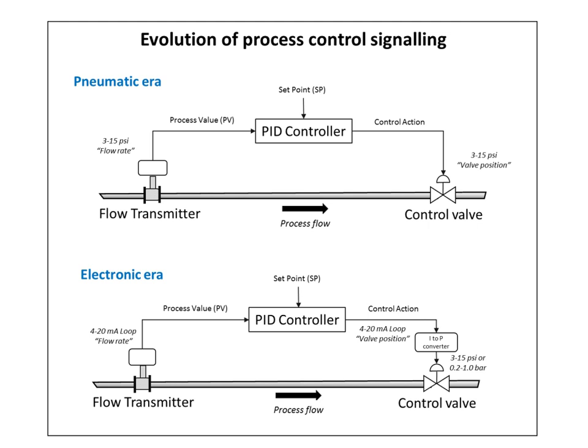Transistor electronics enabled wiring to replace pipes, initially with a range of 20 to 100 mA at up to 90 V for loop-powered devices, reducing to 4 to 20 mA at 12 to 24 V in more modern systems. A transmitter is a device that produces an output signal, often in the form of a 4 to 20 mA electrical current signal, although many other options using voltage, frequency, pressure, or ethernet are possible.